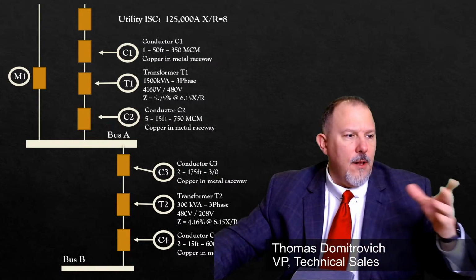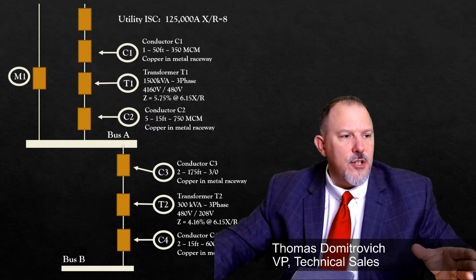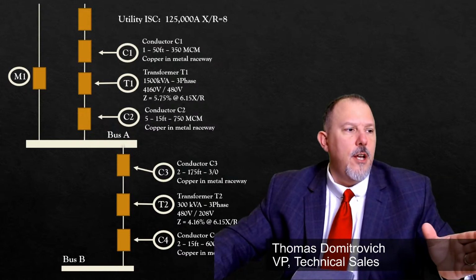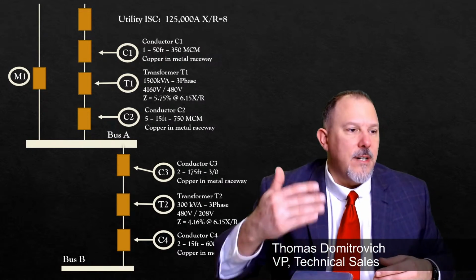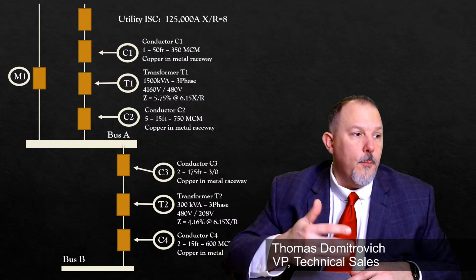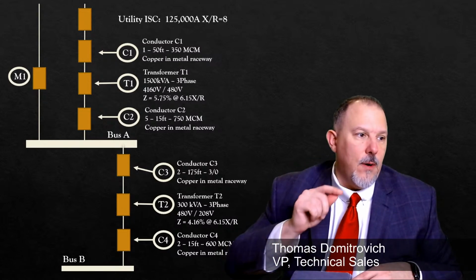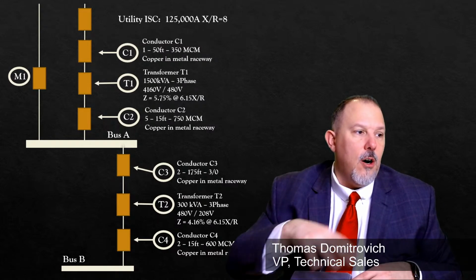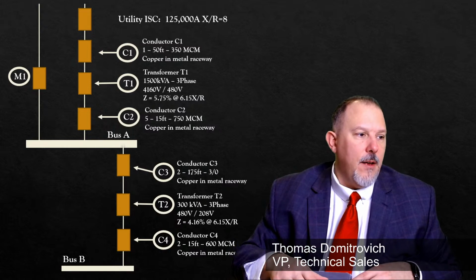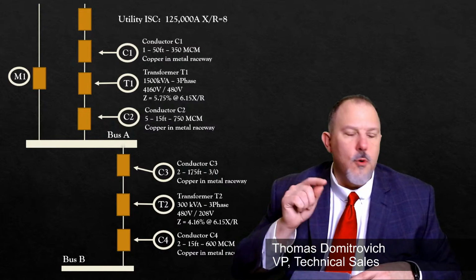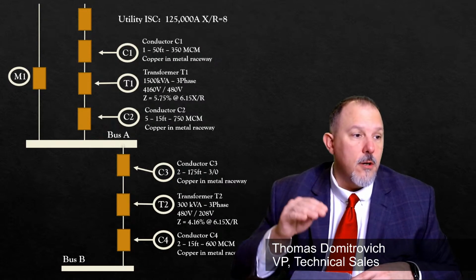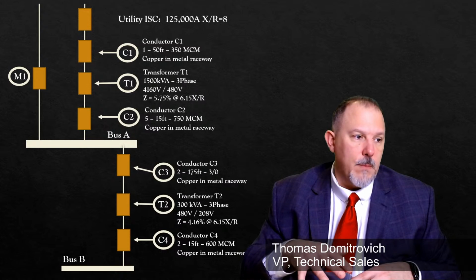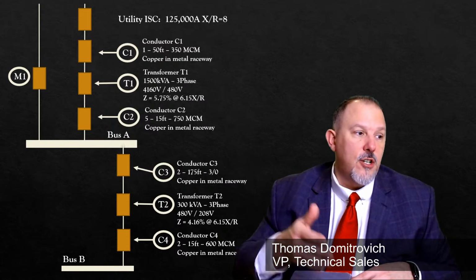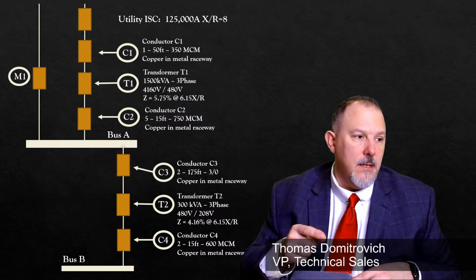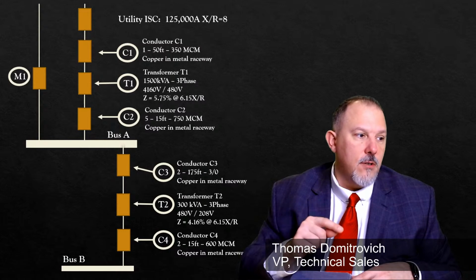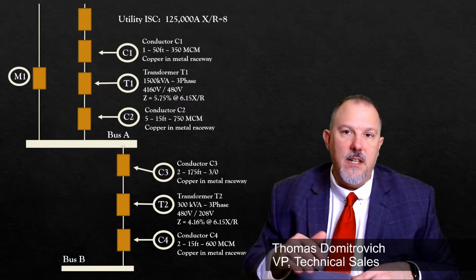So all others 50 horse. Because the initial symmetrical RMS magnitude of the current contributed to a terminal short circuit might be 6 times rated for a typical induction motor, they will use 4.8 times the rated current for the first cycle estimated for the large low voltage induction motors, all 50 horsepower and above. Now, again, it says for this motor group, there is a reasonable correspondence of low and high voltage procedures. For smaller induction motors, all motors less than 50 horsepower, a conservative estimate of 3.6 times rated current, that's an equivalent of 0.28 per unit impedance. First cycle assumption of low voltage standards, and effectively is the same as multiplying the subtransient impedance by 1.67.